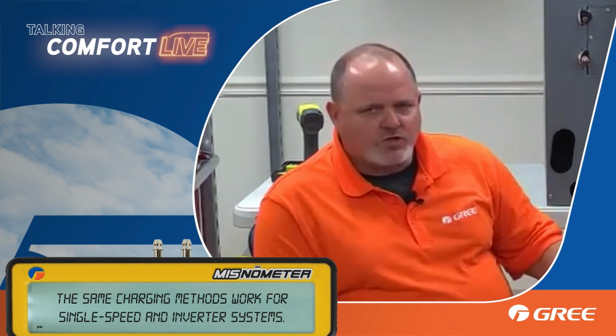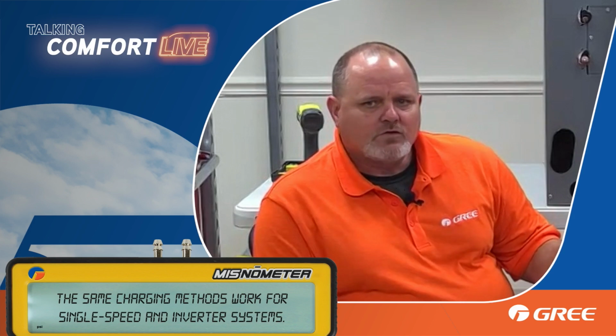So on a new installation, your charge is already in your outdoor unit. So all we really need to do is calculate the charge we need for our line set in our indoor unit. But let's say we're servicing. Now, it's a little different story. We've got to know that calculation for our line set and our indoor units. We're also going to need to know the charge for the outdoor unit.